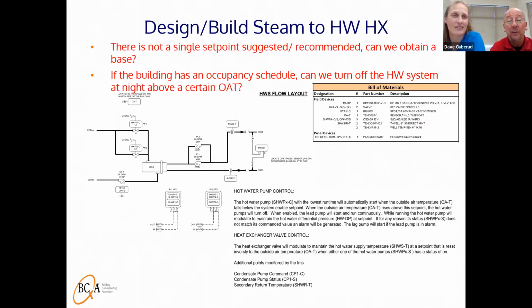So an example here, it talks about the system being enabled, but doesn't really get into detail. So this is an opportunity as a commissioning provider to say, is it just a single set point on off, or does, most reheat systems certainly do have to run when the building is occupied. But is there the opportunity that we can potentially turn it off at night, to save some energy, and if there's a call for heat, then allow the system to come up.